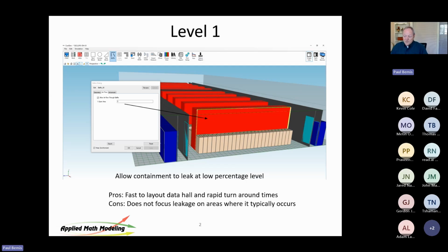And doing it this way is quick. You can lay them out really, really fast, but this one's pretty coarse in its representation. It does not focus the leakage anywhere. It's letting it leak right through this whole surface. And the way leakage is often set, you'll have people say to you, oh yeah, assume 10% leakage. And the question I always ask is 10% of what? 10% of the total amount of air? 10% of the surface area? What's the percentage of? And I've never gotten a clean definition of the percentage.